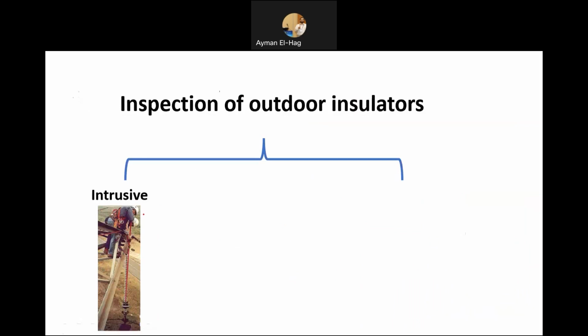The first category of inspection methods, we call them intrusive methods. In the intrusive methods, you have to go there, and either you need to shut down the high voltage lines, which is intrusive in that aspect by actually cutting down the power, or you have to go there personally when the line is energized and do some inspection. Here, for example, the workers are trying to measure the voltage across the string of the insulators to figure out if there is any damage in those insulators. So it's very obvious that intrusive methods are both not safe and extremely expensive because they are not efficient.